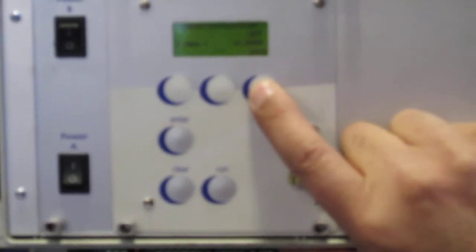So it automatically sees, oh, I've got a high jump in counts. Then it automatically knows that, okay, I've got radiation interference. It jumps back down to the other reading. Your maximum rate, if you're using relays, you need to set those, and it does that with calibration. If you're not using relays, I set them to 0. That way it won't cause any errors. And the same with the minimum rate.